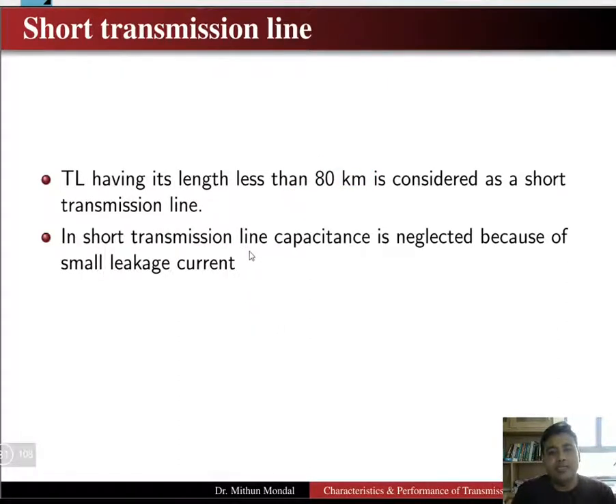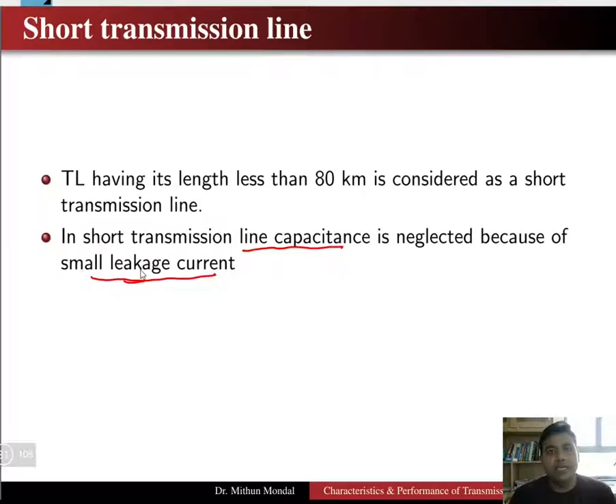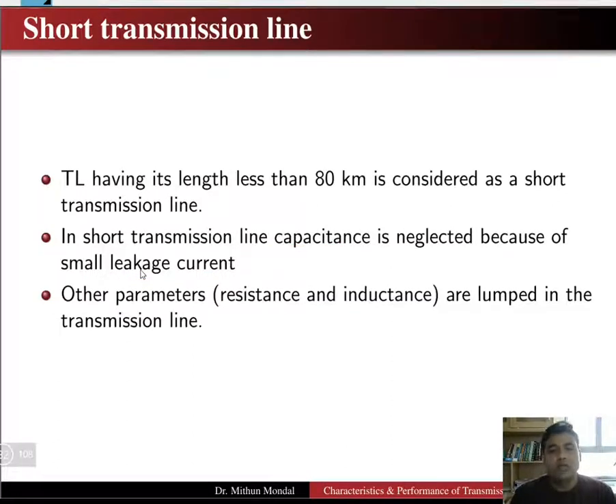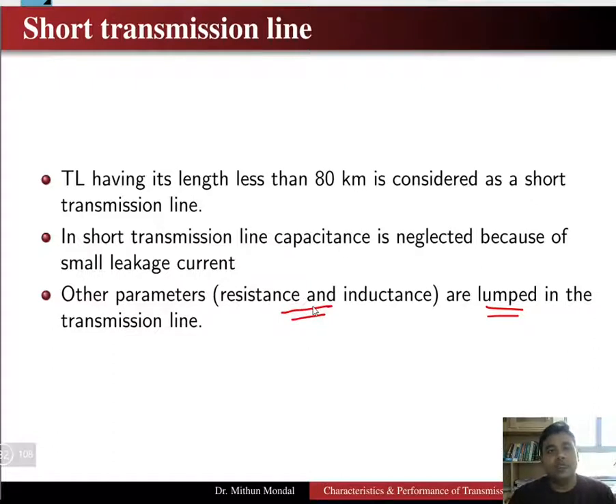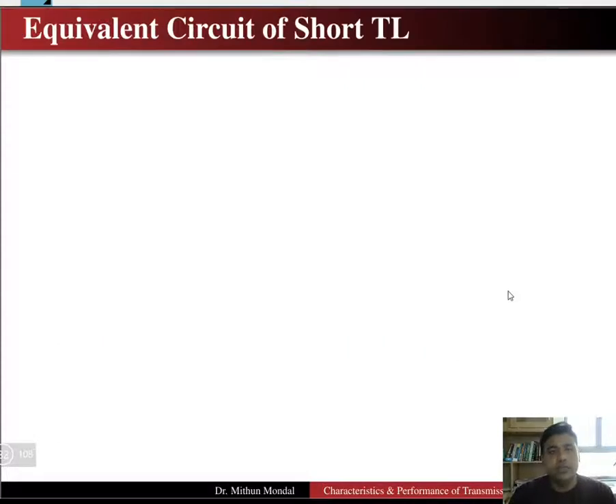For a short transmission line, we neglect the line capacitance because the leakage current is very small. All the parameters will be in lumped form — that is, the resistance and inductance are lumped. In long transmission lines we deal with distributed parameters, but here we use lumped parameters.